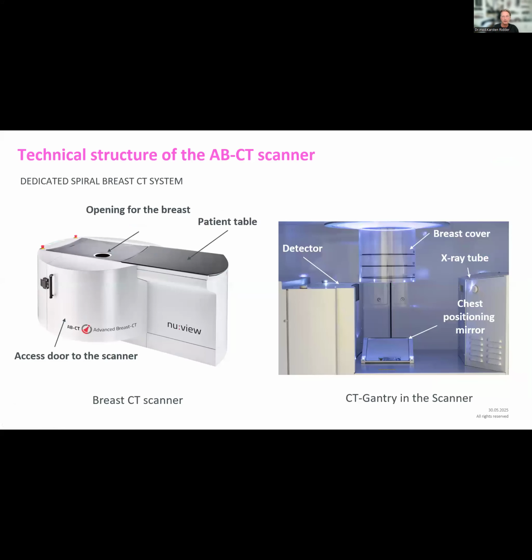And looking at the details, the technical structure, firstly, of the ABCT scanner. This is a dedicated spiral breast CT system. When you open the bore or the compartment, you have an access door to the scanner. You have an opening for the breast and the patient table. And when you open this door, you get this image. You see on the left side the detector, a breast cover, on the right side the X-ray tube, and the positioning mirror on the bottom.